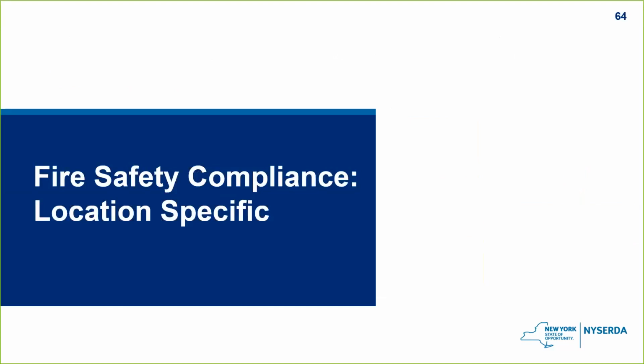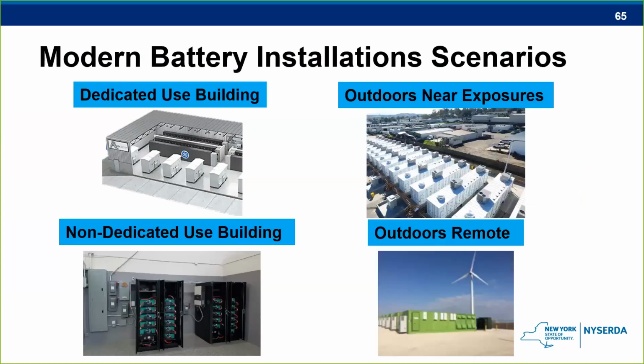Okay, so to review a little bit, we've gone over requirements that all commercial and utility installations will need to meet, as well as some additional requirements based on their chemistry. So lastly, we'll go over different requirements that are needed based on where the system's located. This is an overview of how the code's broken up based on location. We have dedicated use buildings, which is what it sounds like. They're built just for housing battery energy storage, non-dedicated use buildings that might have more than one thing going on, outdoor systems that are near other exposures, and outdoor systems that are remote.